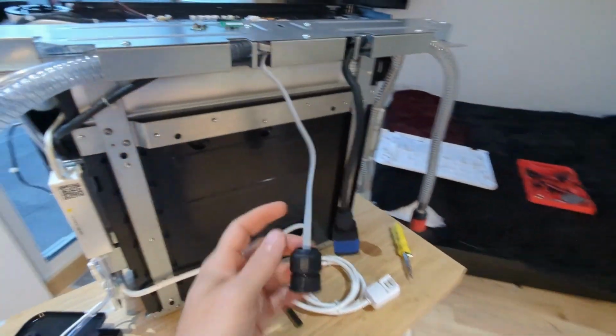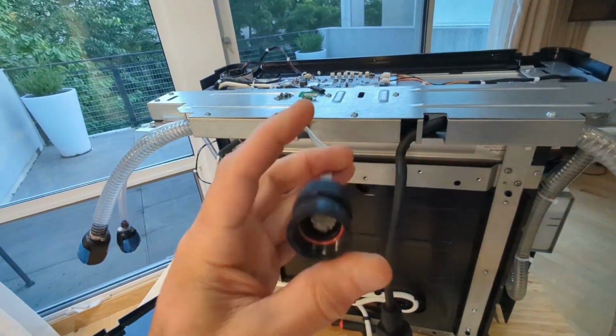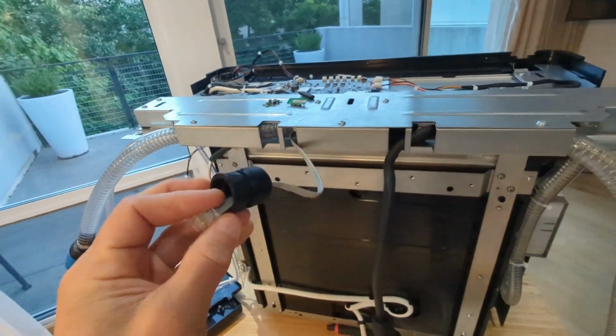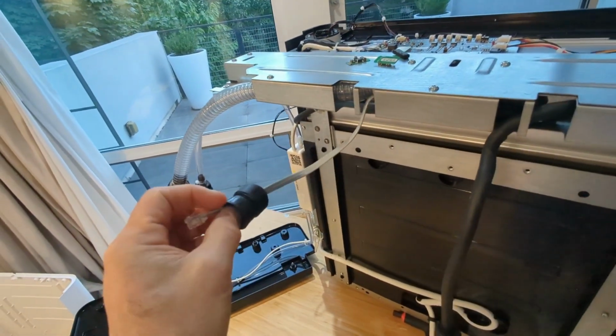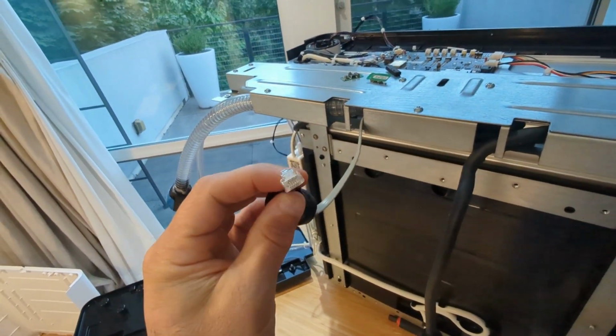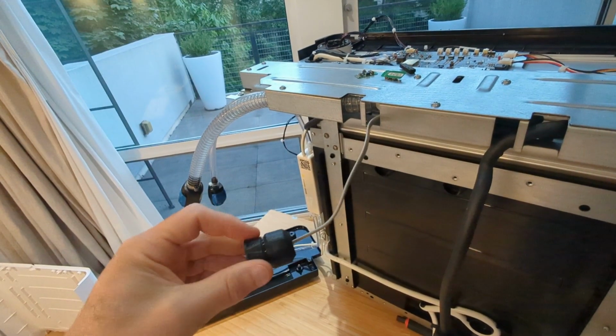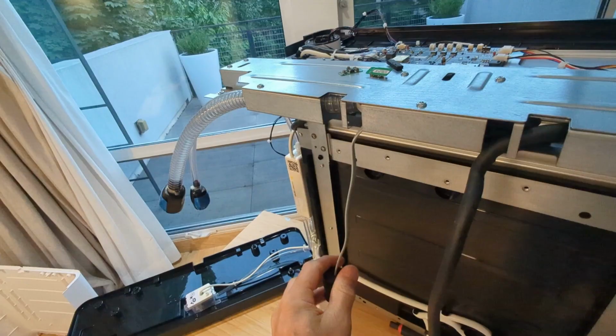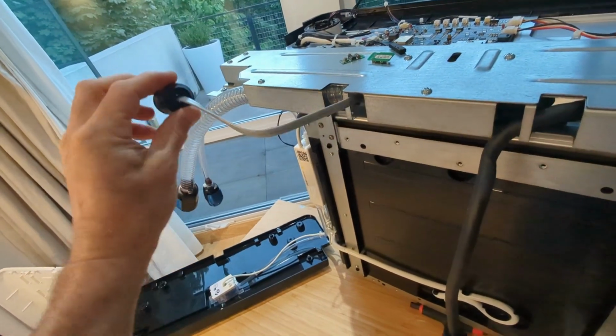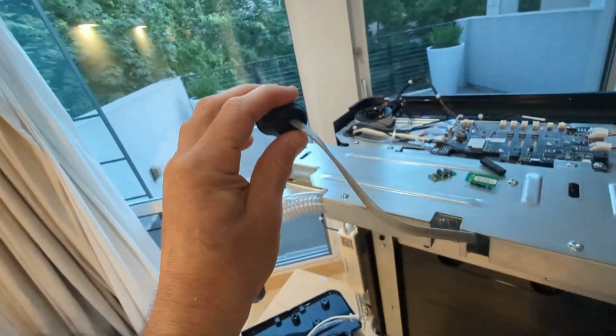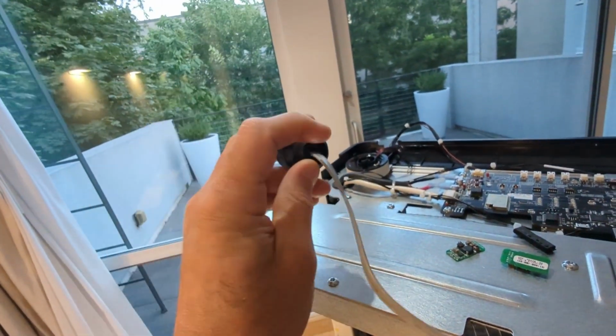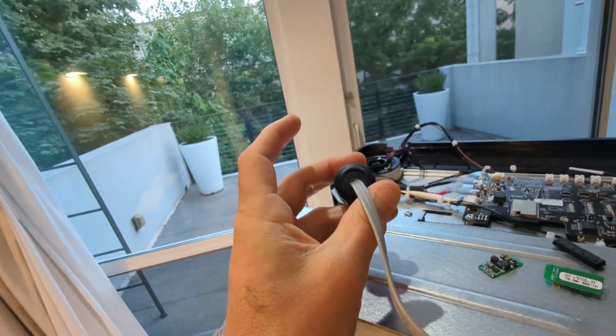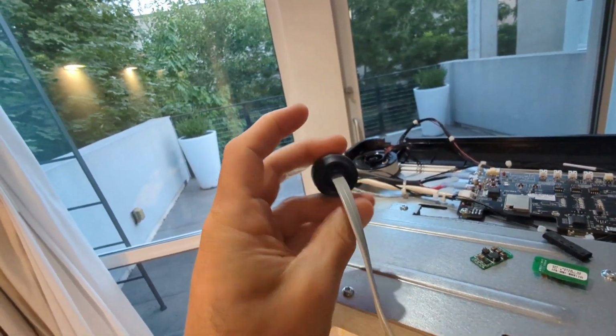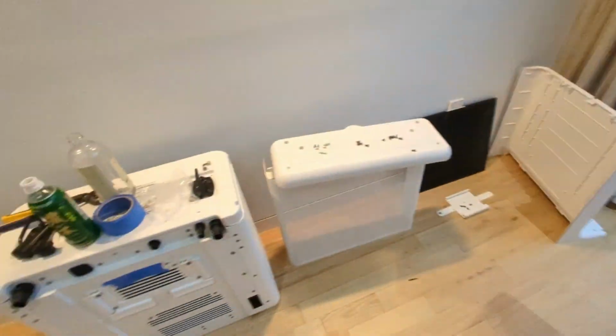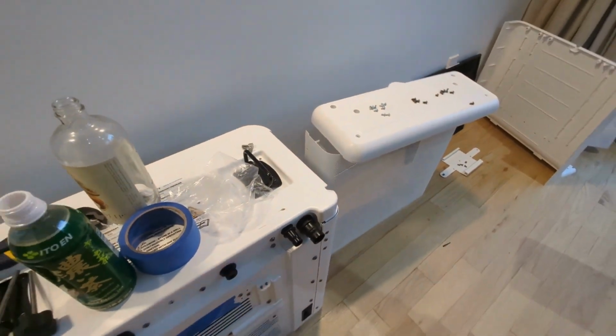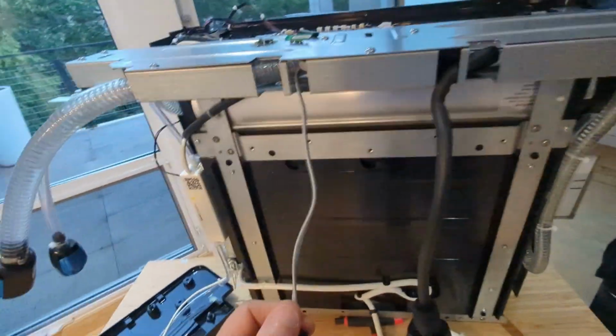More connectors back here. This is the data connection that goes to the outdoor unit to tell it when to turn on and off and to get information from it. It's just an RJ phone plug, which probably was not a great choice for here — I probably would have picked something else. You can see that even though there is a gland here, it is not sealing well. You can see right through it, so water will follow the wire into there, and this connector goes to the outside unit, so that whole thing is outdoors where water can get in and mess it up.